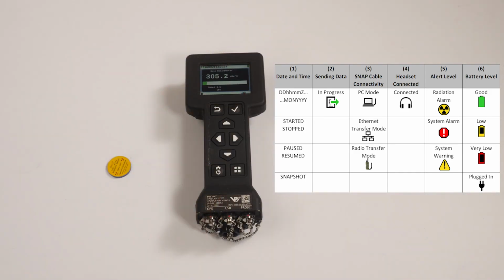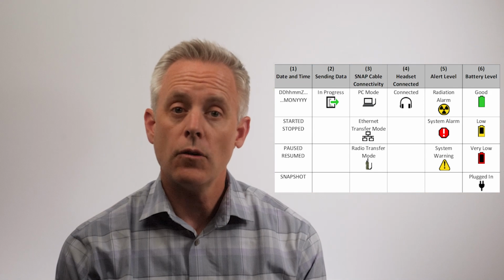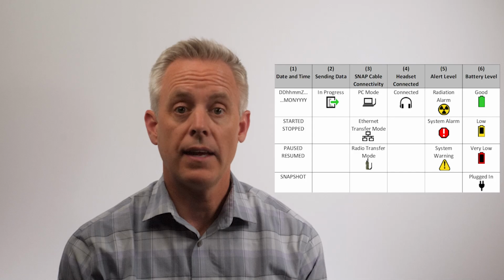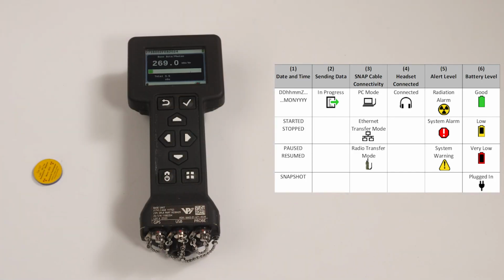The fourth location will display a headset icon to indicate that headphones or a headset is connected. All audio will go to the headset and not to the base unit speaker if the headset is connected. The fifth location is used to display alert icons. There are 3 alert icons, a radiation alarm icon, a system alarm icon, and a system warning icon. The radiation alarm icon indicates that 1 or more radiation alarm thresholds have been exceeded. The system alarm icon indicates an issue with the base unit or an attached probe that needs to be addressed. The system warning icon indicates a system notification that is generally informational in purpose.